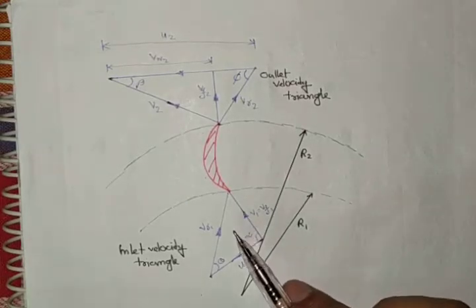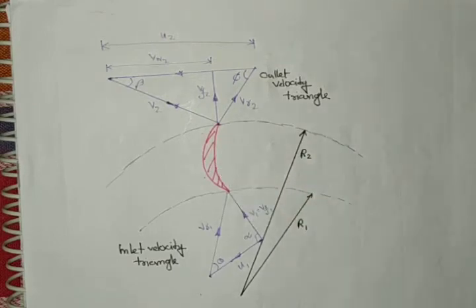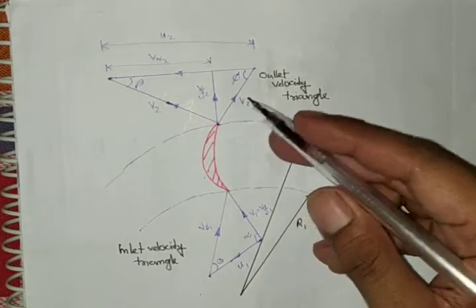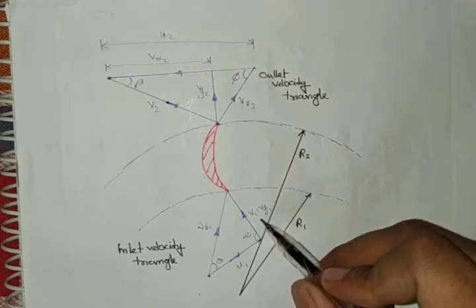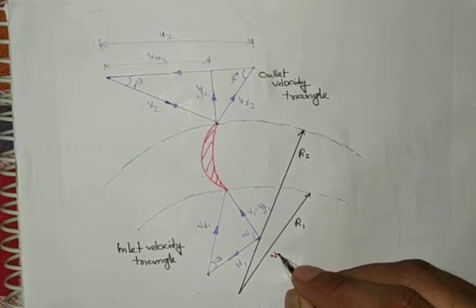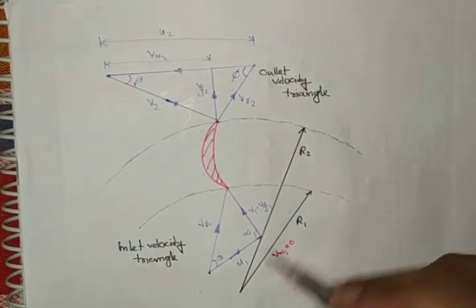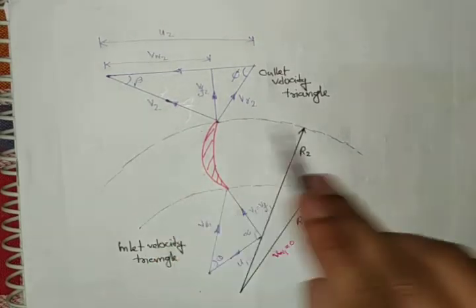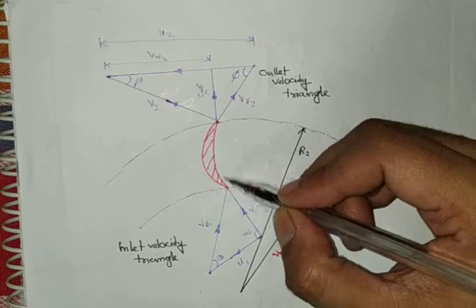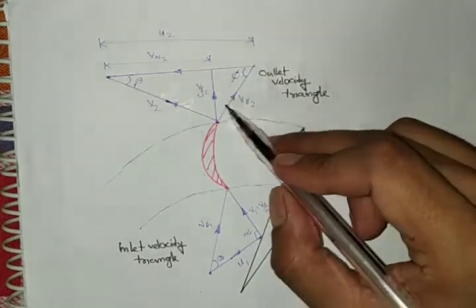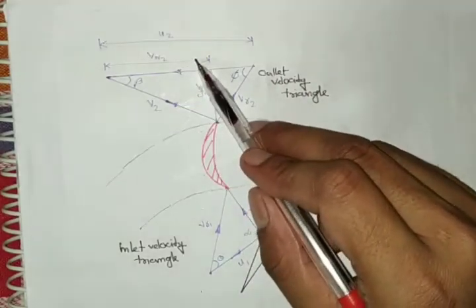This is the velocity diagram of a centrifugal pump, showing the vanes or blades. This is your inlet and this is your outlet. We assume that water or liquid enters radially, meaning alpha is 90°, the velocity of whirl VW1 is zero, and V1 equals Vf1. The outer and inner diameters of the impeller are shown; inside the impeller you will find vanes. After liquid passes through, it comes out at the outlet, and the outlet velocity triangle is given here with its components.